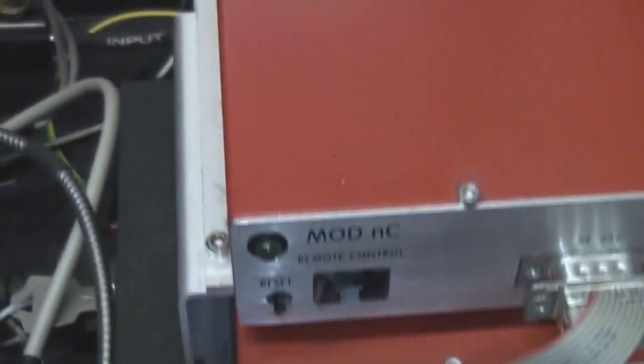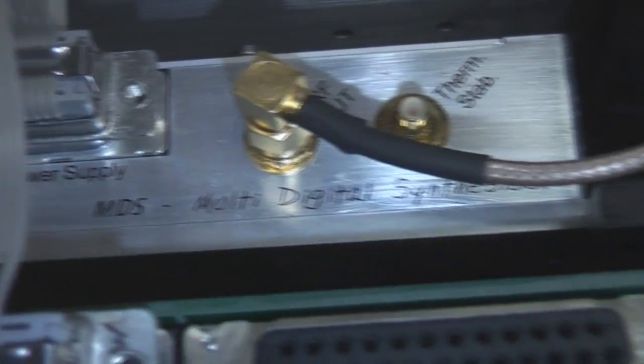So I imagine what's in here are probably things like wavelength specific beam splitters, or possibly some motorised mirrors to flip whichever wavelength you want into the actual beam path. There's a huge great big block here, I've no idea what that is, but that appears, as far as I can see, to be connected to this block here. There are three of these boxes which are all the same, which say MOD nC, which are RF generators for acoustic purposes, but this one's different. This one's got a USB input and it says MDS multi-digital synthesizer, so maybe it produces different frequencies for a different type of acousto-optical device. There's probably something different going on inside this box here, so that's going to be quite interesting.